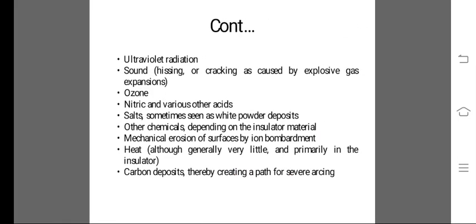The effects of corona include: light and ultraviolet radiation; sound such as hissing or cracking caused by explosive gas expansions; ozone; nitric and various other acids; salts, sometimes seen as white powder deposits; other chemicals depending on the insulator material; mechanical erosion of surfaces by ion bombardment; heat, although generally very little, and primarily in the insulator; and carbon deposits, thereby creating a path for severe arcing.